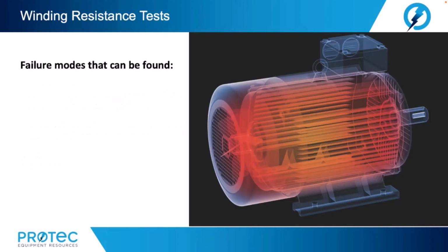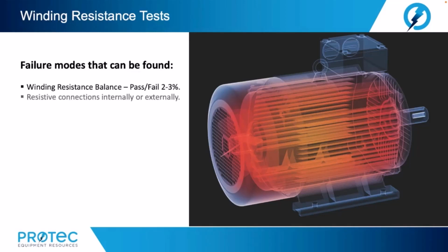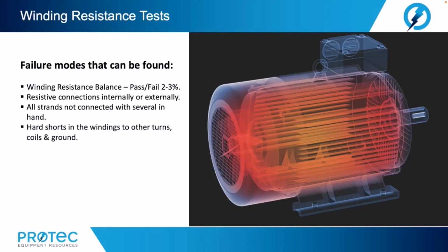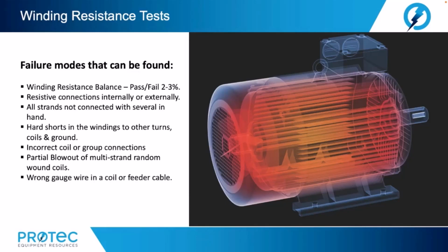All right, winding resistance tests. What failure modes can be found? Well, winding resistance balance with pass-fail 2 to 3%. Resistive connections internally or externally. All strands are not connected with several in hand. Hard shorts in the windings to other turns, coils, and ground. Incorrect coil or group connections. Partial blowout of multi-strand random wound coils. Or wrong gauge wire in a coil or feeder cable. Possibly wrong turn count.